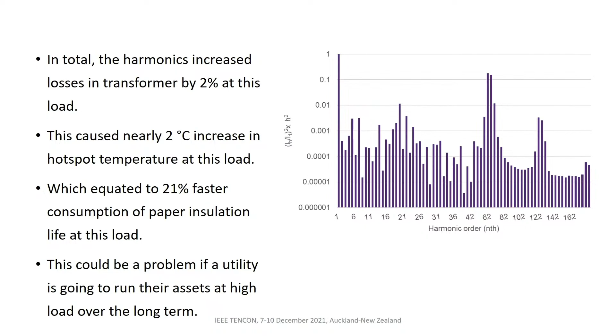In terms of our suggestions and what we think should be done about this, we can really see that there's a need for more monitoring and calculation methods of harmonics to determine what is actually happening at the transformer. Now, some transformers might have monitoring on them. A lot of them here, the smaller ones, don't. So we can see a role for calculation methods to try and find where these pinch points are on the system. We're not talking about every single transformer having monitoring. It's just that we can see methods to detect across the grid where there could be harmonic heating.